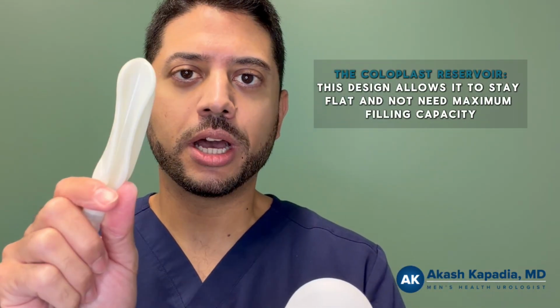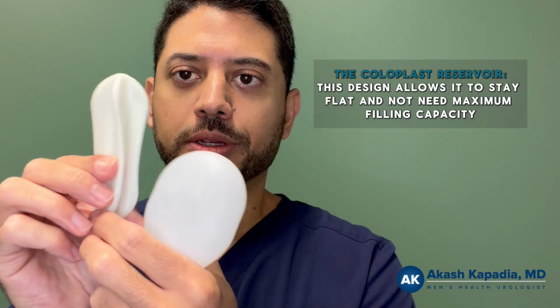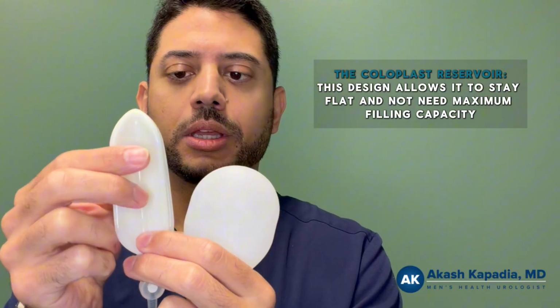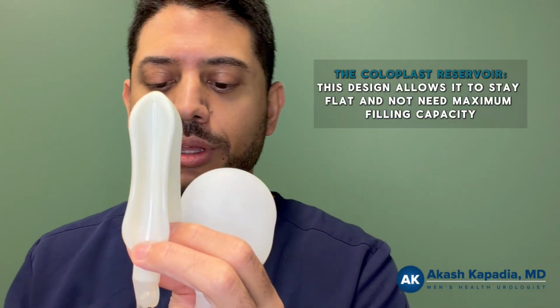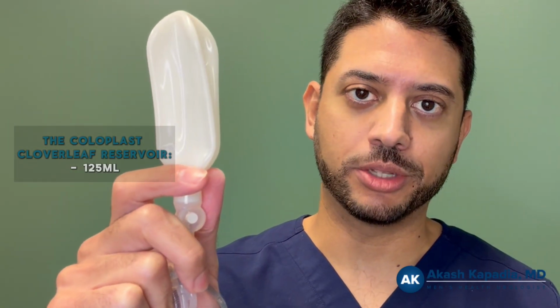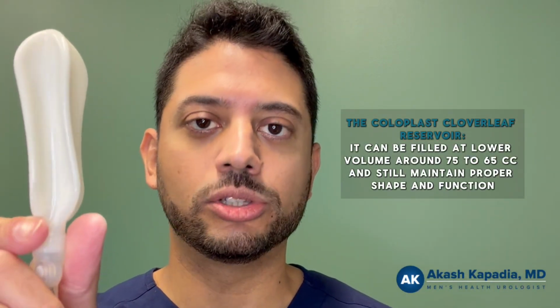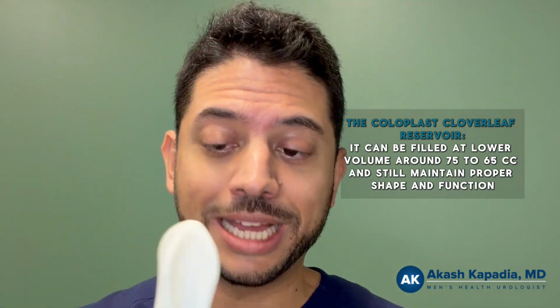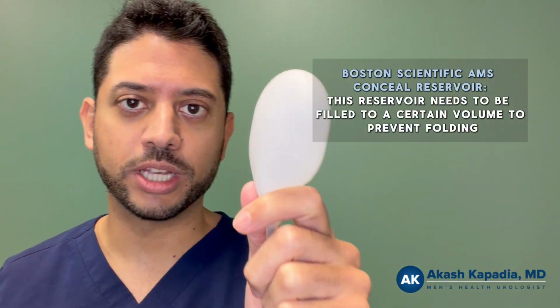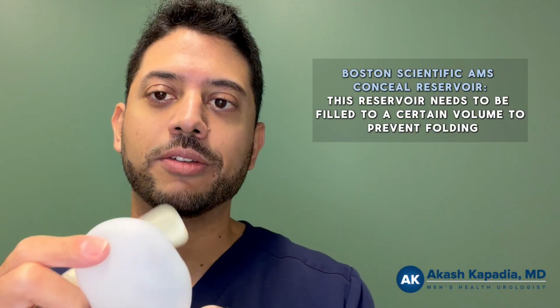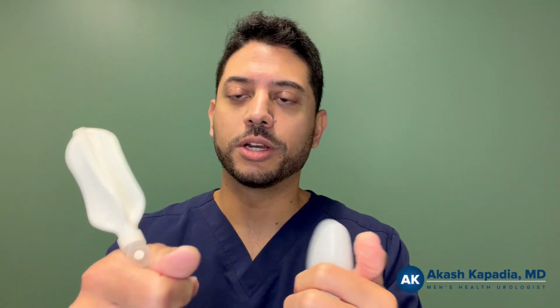The reason that the cloverleaf reservoir is designed in such a way is because it can assume a very flat shape, much like the Conceal, when it is empty. And not only that, but because of the design that they've created, this reservoir does not need to be filled to its maximal capacity. So this one goes to 100 mLs, this one goes to 125 mLs. However, this can be kept at a much lower volume, as low as 75 or 65 cc's, whatever the penile implant needs, and it'll maintain a nice shape without affecting the function of the reservoir. Whereas this particular reservoir does need to be filled to a certain volume to prevent it from folding. That's the main concern. The reservoirs can fold, whereas this does not do that. So this allows more flexibility in the volume that can be put into the reservoir. This allows for a better concealed profile.